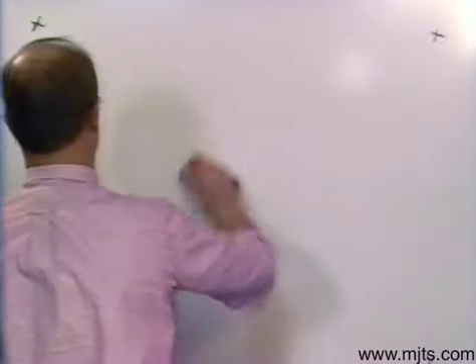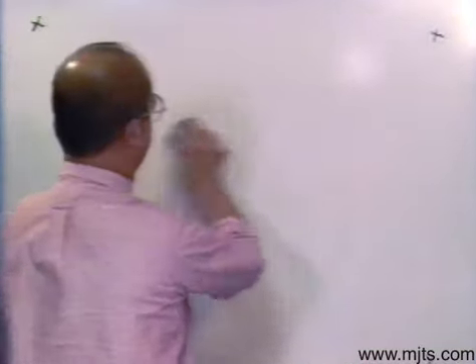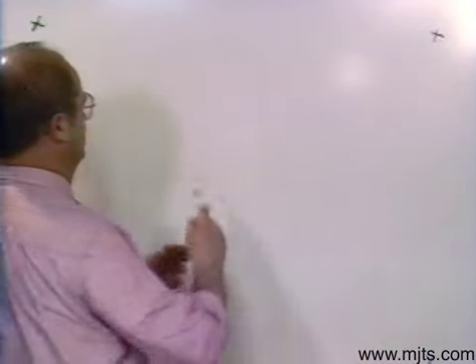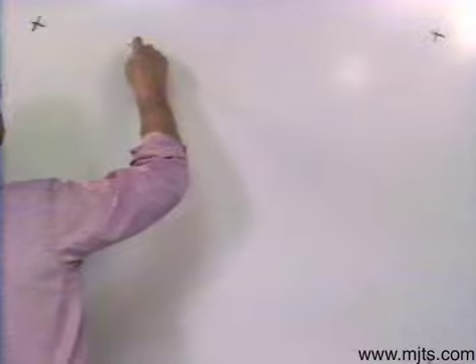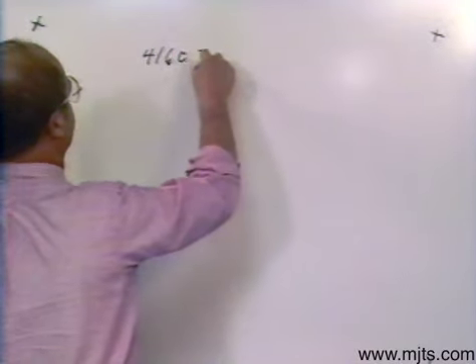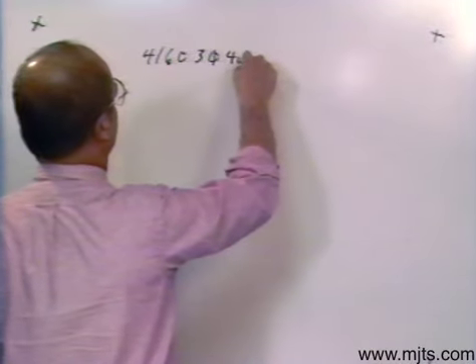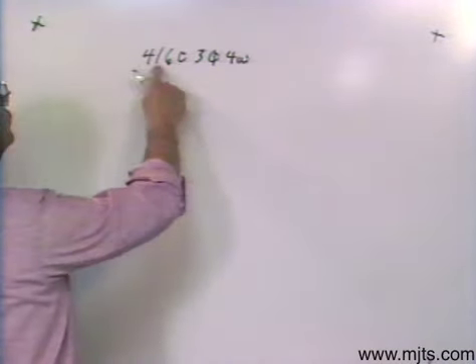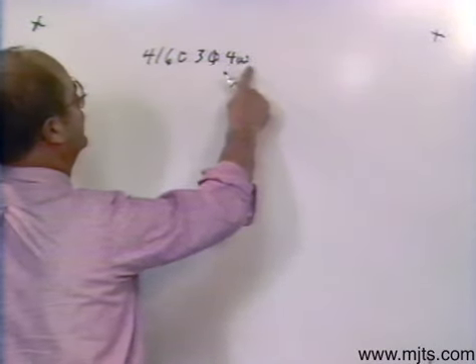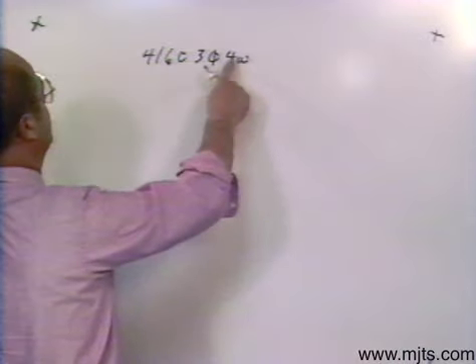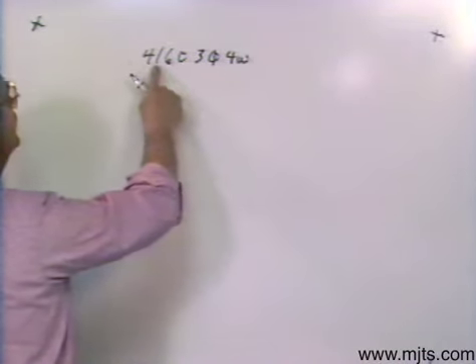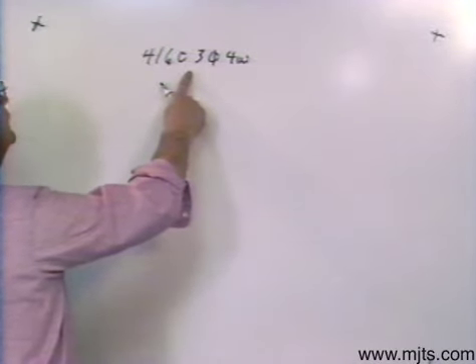Now, let's say that on the high side I know what my system voltage is. Let's say on my high side I know that I have a 4160, 3-phase, 4-wire. I look at that and I know this 4160 is a phase-to-phase value. I look at the 4-wire and I know it's a Y system. Then I know that what I have available is 2400 to ground and phase-to-phase 4160.